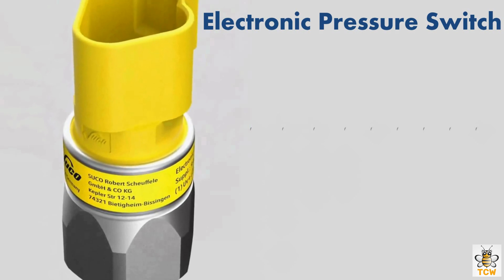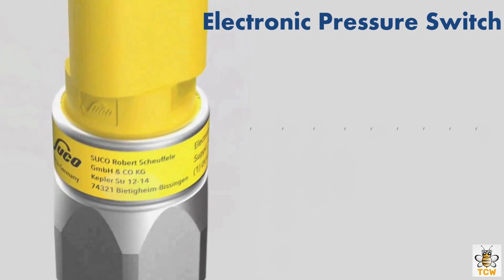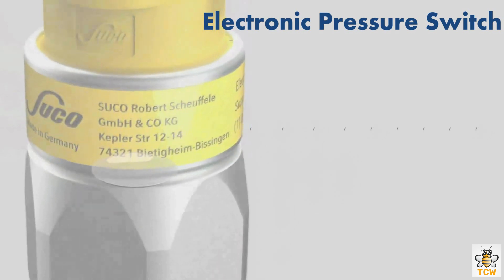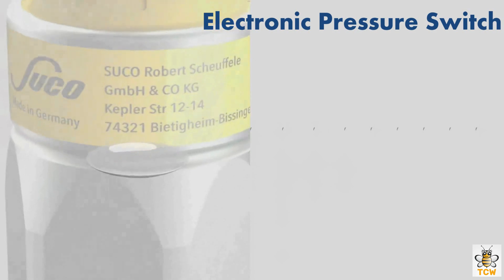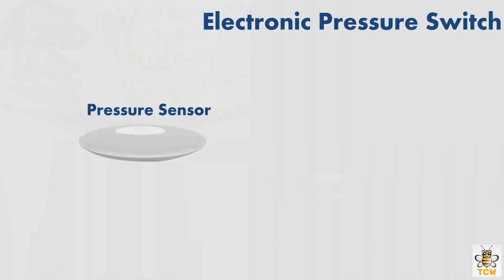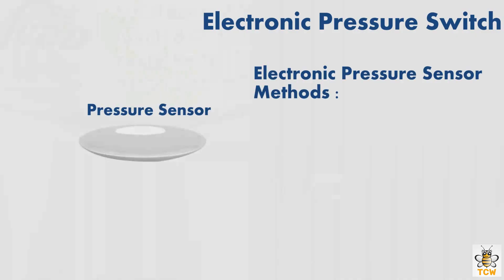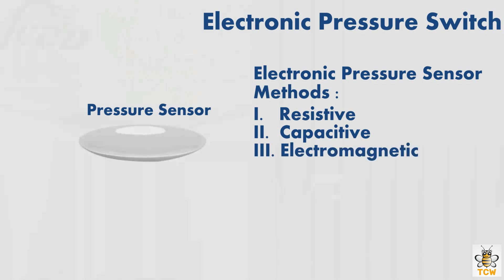The electronic pressure switch works primarily by changing the electrical properties of the material used as a pressure sensor. This includes the electrical resistance of the materials, called the resistive method; or the ability of materials to store electrical energy, called the capacitive method; or changing the magnetic properties of the materials, called the electromagnetic method.